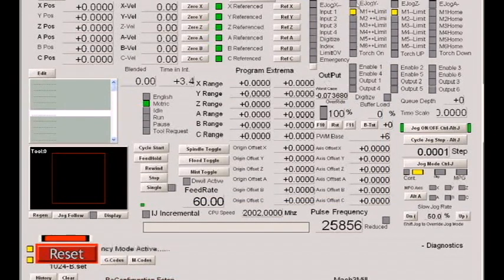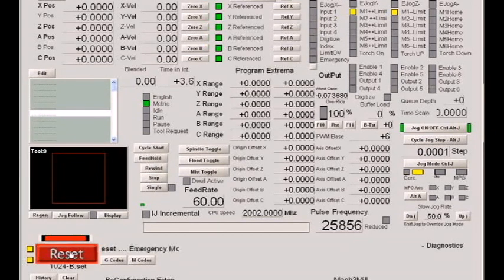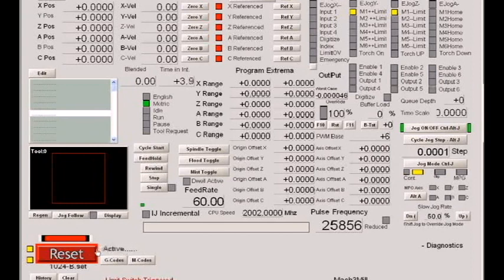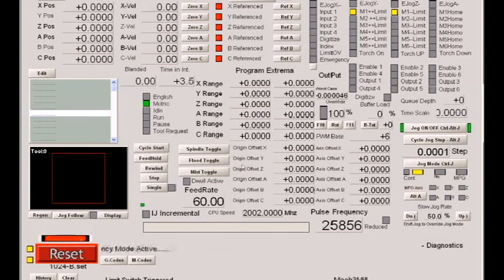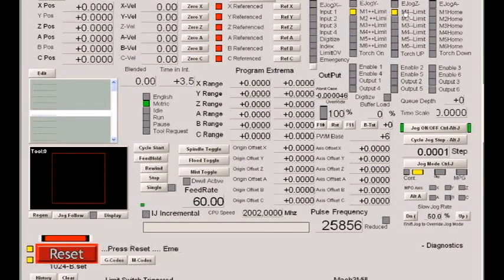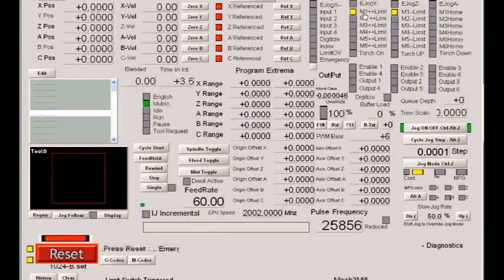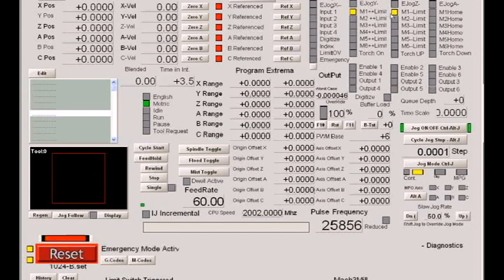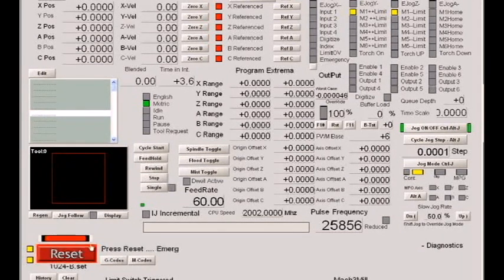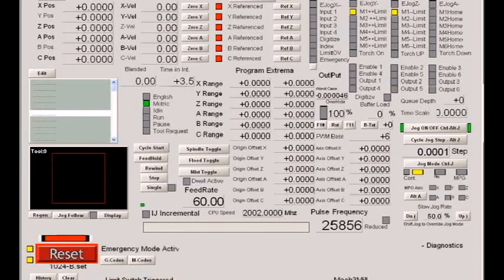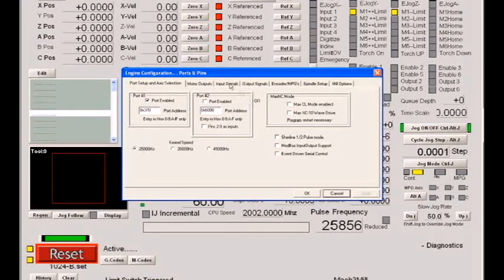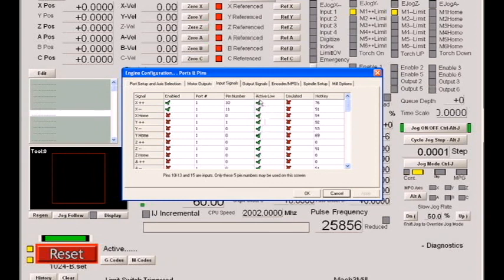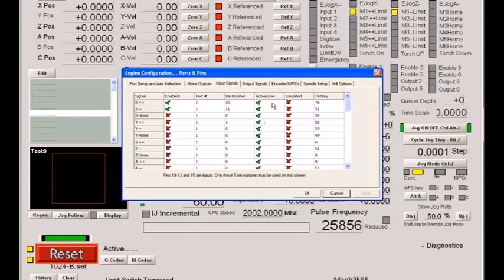Also we can't reset the control. No matter what we do, we get a message saying limit switch triggered. The reason for this is that these LEDs should not be on. Any LED lit up in the input section is telling you that that signal is active, and obviously if we have an active limit signal, we're going to trip an e-stop and we should not be able to reset.